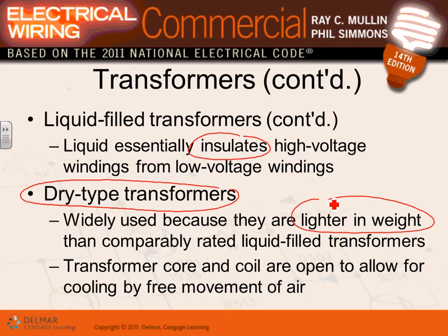So transformers, the cores and the coils are open. They design them in a way where they're open to circulating air, so the air will circulate and cool them. The single most important thing about a transformer is being able to cool it. These beasts are being cooked by a lot of energy and they generate heat, and if you do not dissipate that heat, it will kill that transformer.